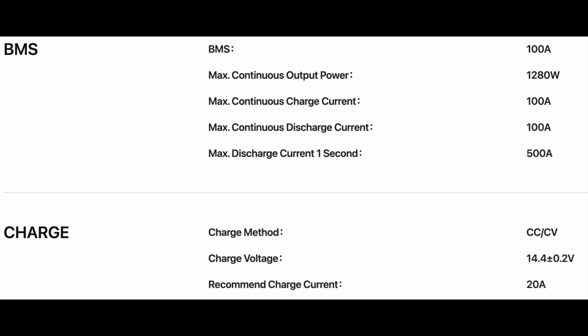The continuous charge current max is 100 amps, and the continuous discharge current is also 100 amps, but the recommended charge current is 20 amps, so keep that in mind. As for surge capabilities, this battery is capable of discharging a max of 500 amps for up to 1 second.